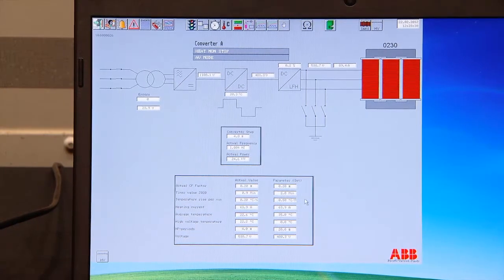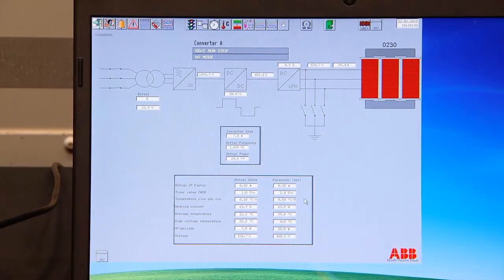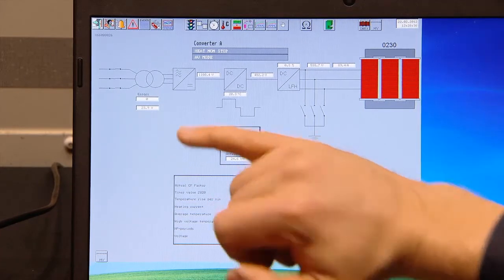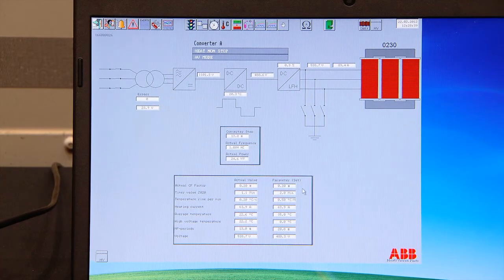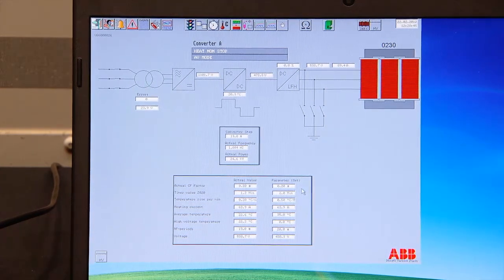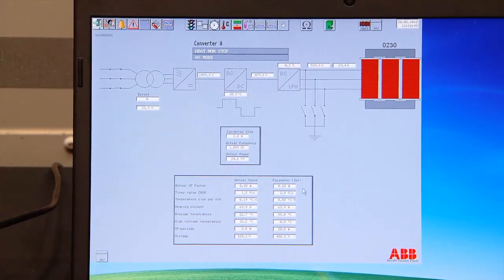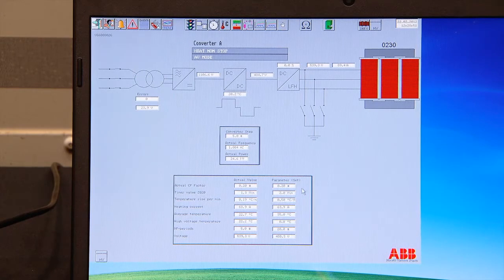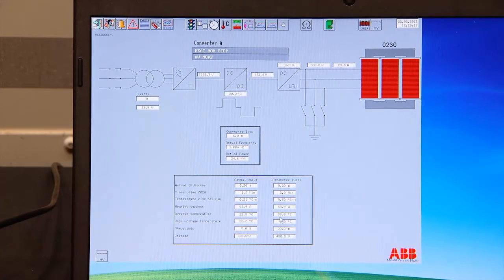That 20 cycles, is that standard? That's standard, yeah. And it's 20 cycles, so the time is depending on the frequency you have. If you have 1 hertz, it's 20 seconds. If you have 0.5 hertz, it's 40 seconds. We can see here our set temperature, 35 degrees. Remember, we put 40 degrees as our set temperature, but we have 5 degrees before we're reaching our set temperature. We will do the high voltage temperature reading, just to give it a chance to kind of level out. If we are too high on the low voltage side, we will not be extremely much too high.